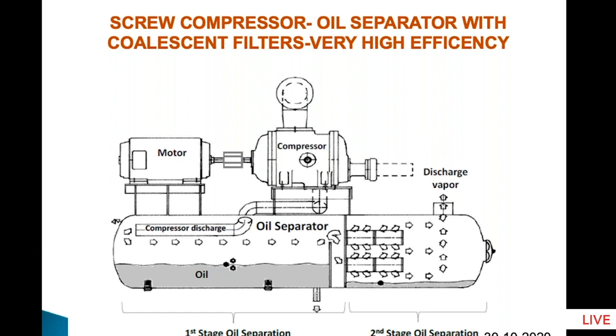I would say in air compressors, when we use these kinds of oil separators, the air is so free of oil that we call it breathing quality air. So a person can breathe that air. So you can imagine how efficient the oil separator is. But as you know, as the efficiency goes up, the cost will go up. But it is a one-time investment, and your oil draining problems from the system will be reduced.